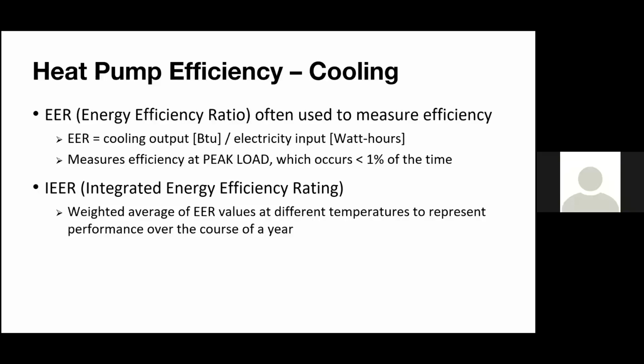And with a heat pump system with variable speed, you might actually be at 50% load, right? And it doesn't work linearly at all. So you might be at 50% load, but you're not going to have 50% power input. We're going to be ramping that compressor way down low to the point where you might only have 25 to 30% input. So EER really doesn't tell the full story. So that's why we have IEER, which is Integrated Energy Efficiency Ratio. What this does is take a weighted average of the EER values at different temperatures. It's going to take the different temperatures, the different loading standpoints, and then it's also going to have time weighting associated with that, right?